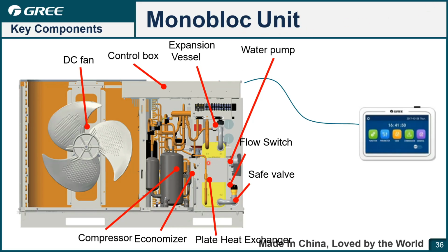So you can see the structure of our unit is a little bit different. Here is the compressor and economizer here. PHE for hot water, safety valve, flow switch, water pump, and this is expansion vessel. For the monoblock type, the expansion vessel is different with the split and all-in-one. It looks like a cylinder, like a tank, and this is control box and DC fan. And for the wired controller is external, not built in, so you need to prepare a cable connects with the PCB of our units, so the customer they can operate on the controller.